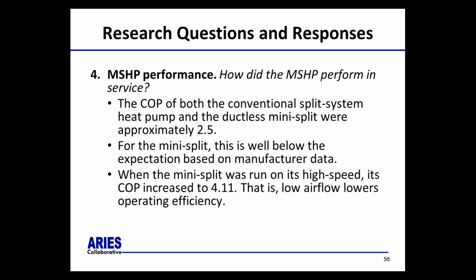How do the mini splits perform in service? You heard about the COPs. Both the conventional and the ductless were about 2.5 before we started investigating why. That is well below the expectation from the manufacturer's data, and this is probably true for any mini split. When we changed the setting to high speed, which is one of the core findings, we got in the neighborhood of what the manufacturer was estimating. So these small things do matter, and how you set things up is important in terms of achieving performance goals.